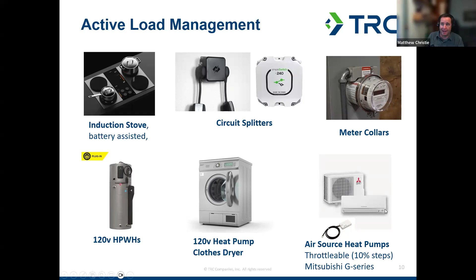And then new, this one's very new. Mitsubishi has a series of heat pumps that can be throttled back. So instead of turning off, like these other ones, circuit splitters, it's go or no go, turn off or turn on. Meter collar, go or no go. These ones will basically say, okay, I'm running hot, turn down 10%. Still hot? All right, 20%. All right, 30%. They'll throttle back in 10% increments down to about 40%. And then they say, okay, now we'll just cut it. That can be used as a way to throttle back without inconveniencing any other loads you're pulling from.